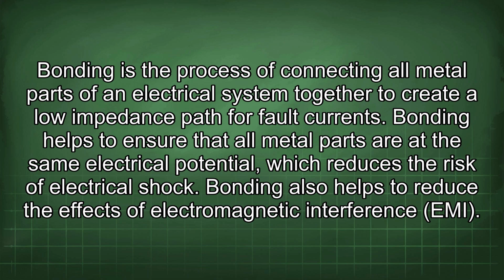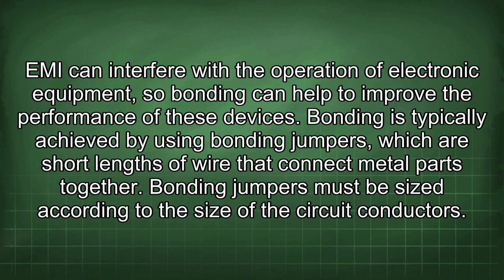Bonding helps to ensure that all metal parts are at the same electrical potential, which reduces the risk of electrical shock. Bonding also helps to reduce the effects of electromagnetic interference (EMI). EMI can interfere with the operation of electronic equipment, so bonding can help to improve the performance of these devices. Bonding is typically achieved by using bonding jumpers, which are short lengths of wire that connect metal parts together. Bonding jumpers must be sized according to the size of the circuit conductors.